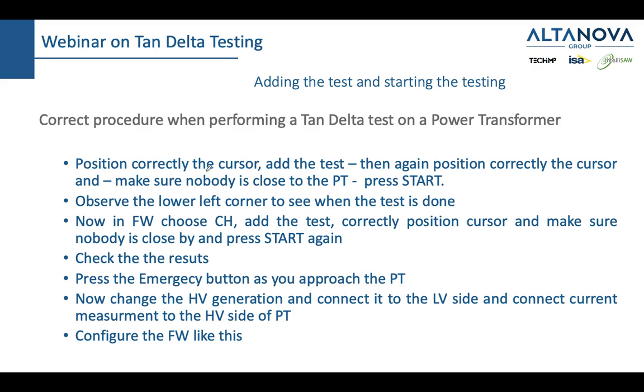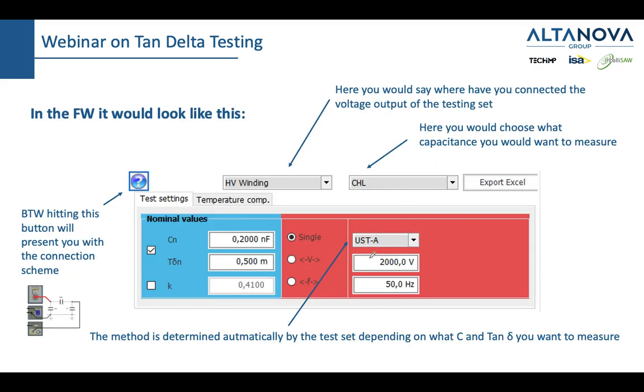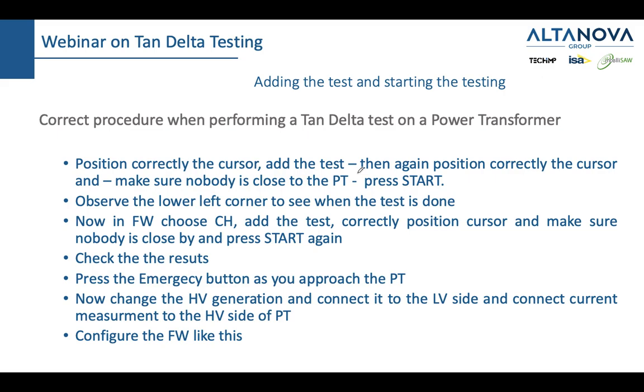As you press start, you would observe the lower left corner, and you would see when the test is executed. First, you would have the stage of load evaluation, then calibration, and then measurement. And actually, we're doing two measurements, and I will explain next time why. And when the test is done, you would go back to this screen, drop this menu again, and choose CH. By choosing CH, you would again make sure that nobody is close, press start, and check the results.